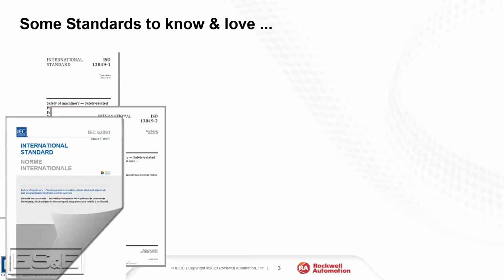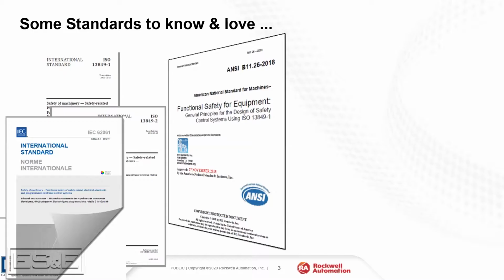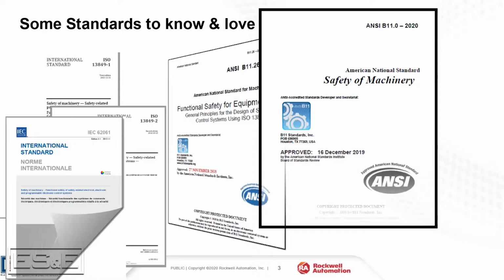There's a relatively new ANSI standard. So this is a U.S., North American standard, and it's called B11.26, and it clearly references and describes functional safety in terms of 13849 part one. I just want to make the point, this is definitely in the ANSI language. This is not just for Europe anymore. This is definitely part of the American engineering standards. ANSI B11.0 was just updated and released about a year ago. This is the basis of risk assessment methodologies and some of the overall system design. So this is a very useful standard to know and use.